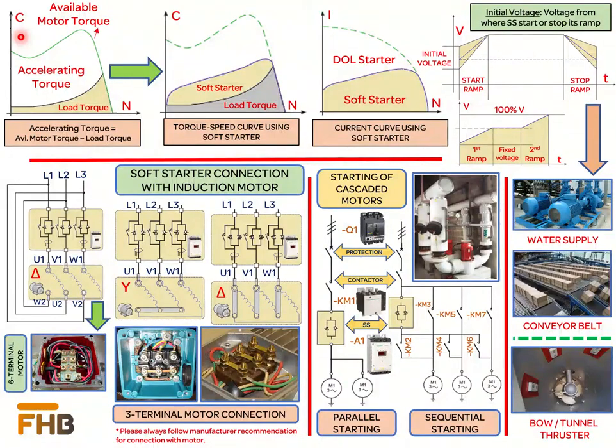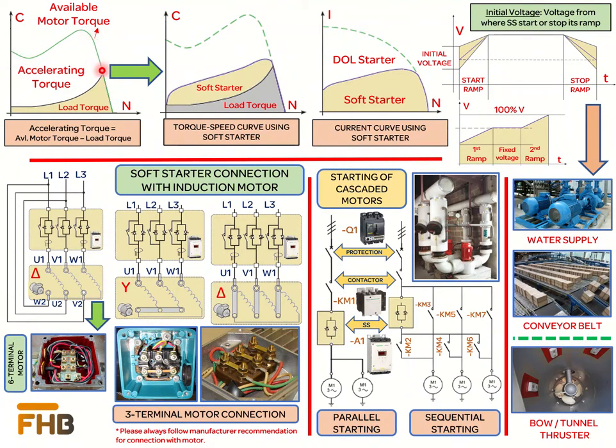Induction motors are used in industry to drive a variety of different applications such as compressors, conveyors, mixers, and different kinds of pumps. These different loads exhibit different loading conditions for the motor. For the motor to accelerate, it is required to be stronger than the load itself. When you look at the torque-speed curve of the induction motor, the load torque is the direct braking force on the motor's shaft. For the motor to drive the load, the motor available torque should always be greater than the load torque. Therefore, the accelerating torque is the difference between the motor available torque and the load torque.